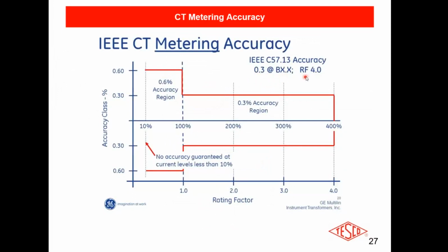And then you have a rating factor. It's really called a thermal rating factor, but we shorten it to rating factor. In this case, it's 4.0, and that's fairly standard. This is a pretty plain vanilla instrument transformer, okay? And I stole this particular one from GE. But again, there are several manufacturers. They're all very good at what they do.